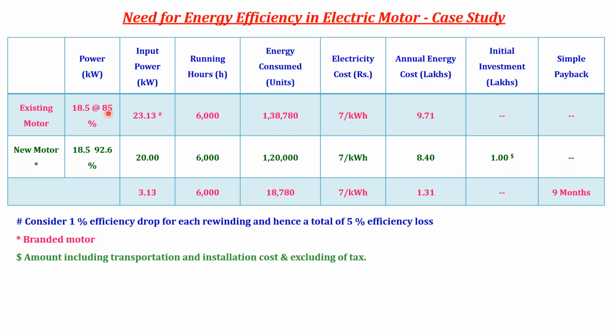Assuming that you have 85% efficiency, it's a nameplate efficiency, but it has been rewound 5 times. So I'm taking a lesser value, because even for one rewinding the efficiency will drop. I'm taking a very least value of 1%, so 5% is the efficiency loss. So it's 80%, and the power input is going to be 23.13.